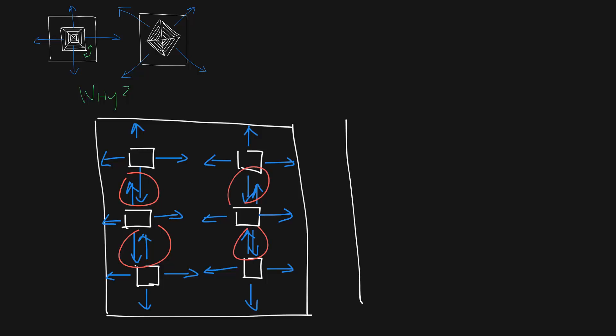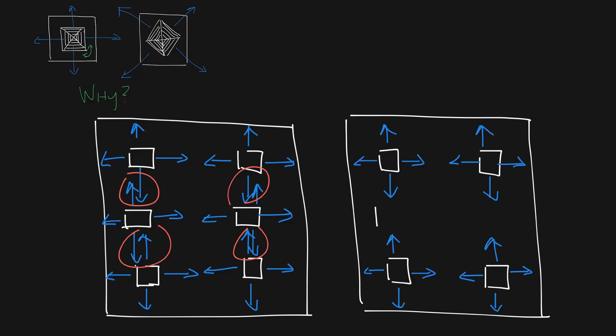So what you could do instead is let's put our four diffusers back in the space. Now you take the two diffusers between them and put them in a corner blow pattern so their airflow goes like this.